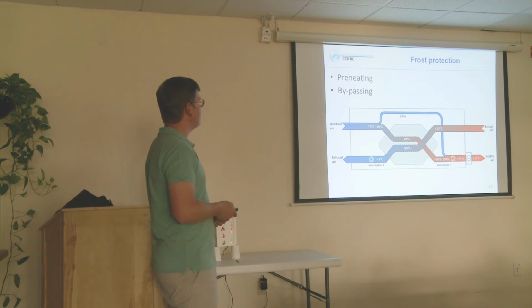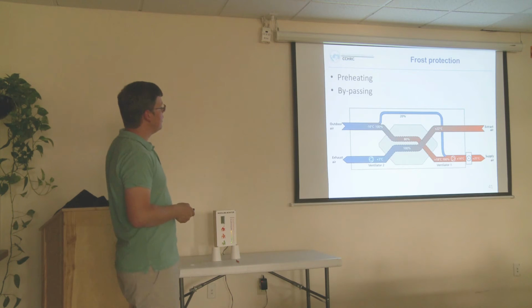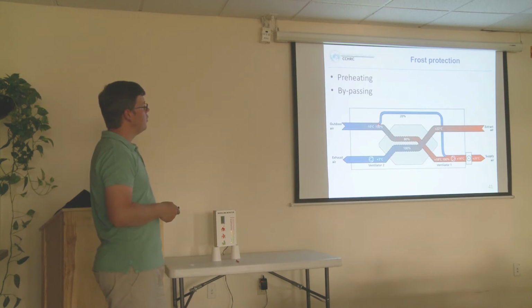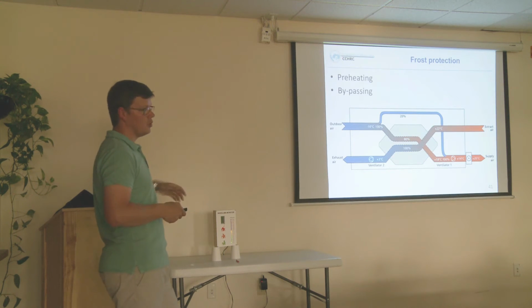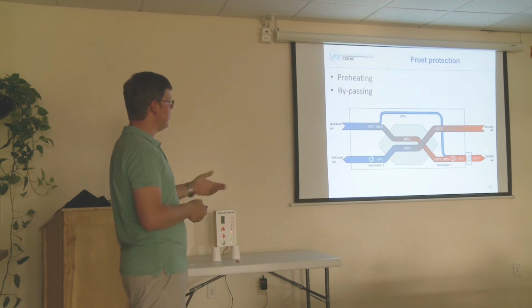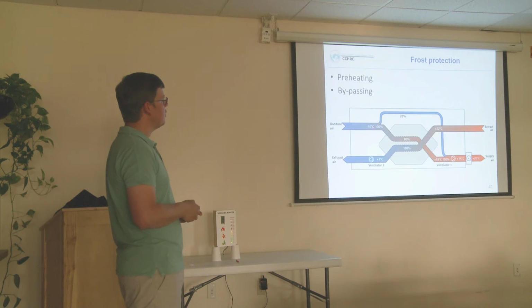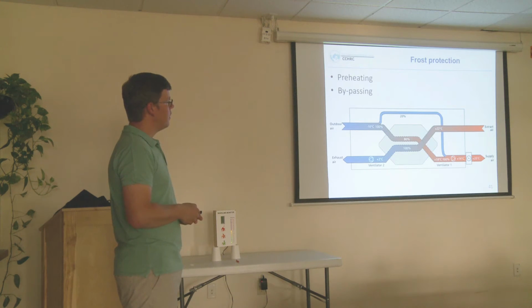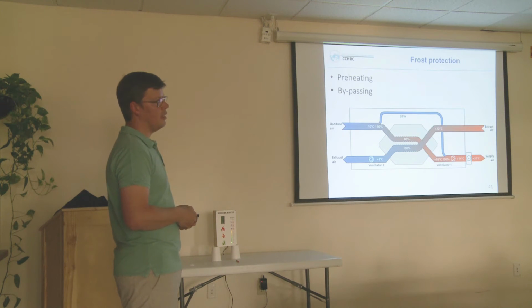Another strategy is bypassing. That is basically a certain amount of fresh air will be sent around the core, so there is more warm air going through the heat exchanger than the cold air, and therefore there eventually will be melting in the heat exchanger. Of course, the ratio will vary according to the outside temperature. So if the outside temperature is too low, you might actually get 100% of the fresh air going bypass to the room, and only the warm air going through the heat exchanger, trying to melt all the ice. Having this strategy, you should have a heater here, which then heats the air before it goes to the room, because otherwise you could get 40 below air blown into your room.